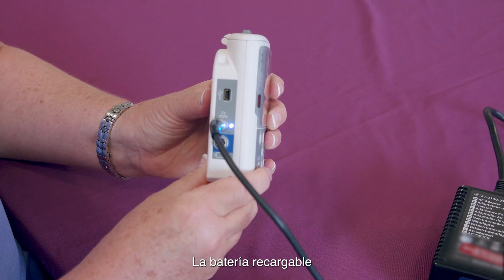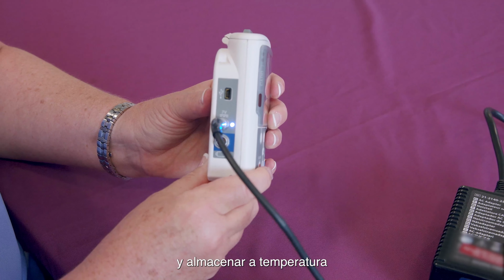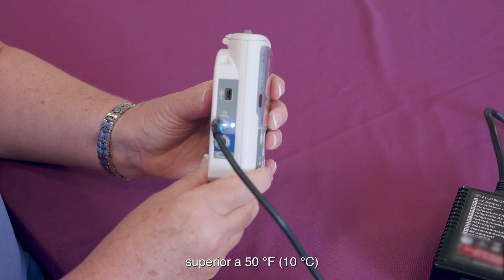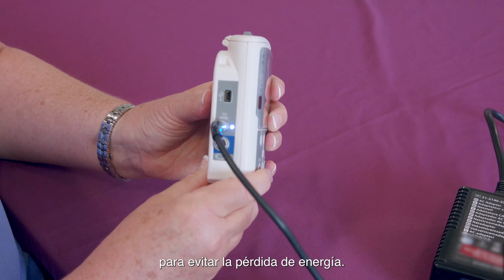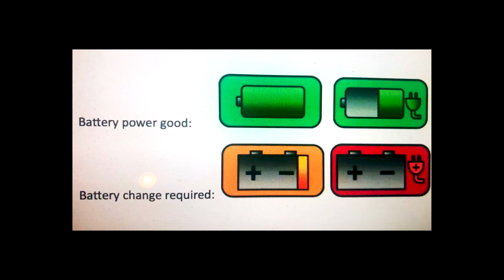The rechargeable battery should be used, charged, and stored in a temperature above 50 degrees Fahrenheit to prevent power loss. The pump should be in the off mode to change or install AA batteries. You will know it is time to change your AA batteries when the battery indicator on the pump screen turns yellow for low battery or red for depleted battery. The CADD Solis pump must be stopped and powered down before changing batteries.